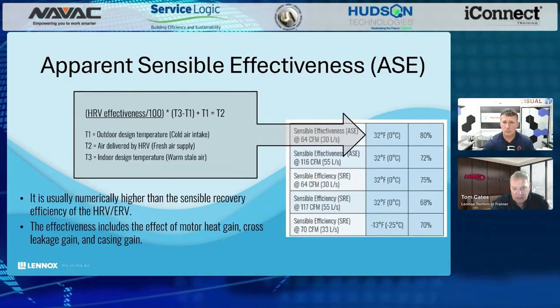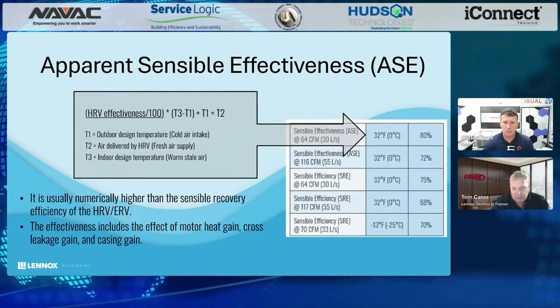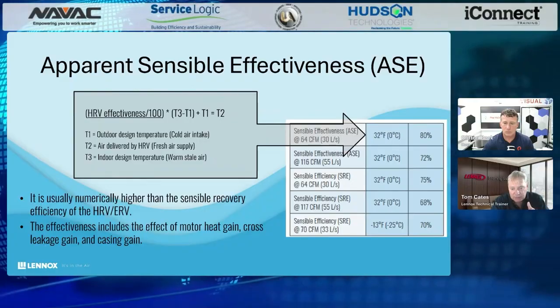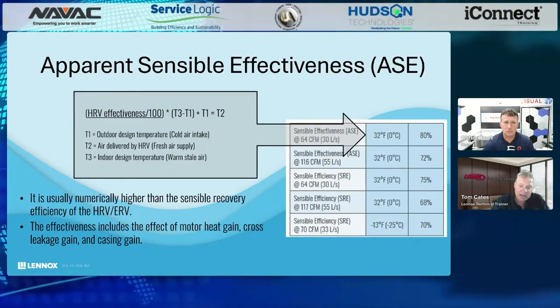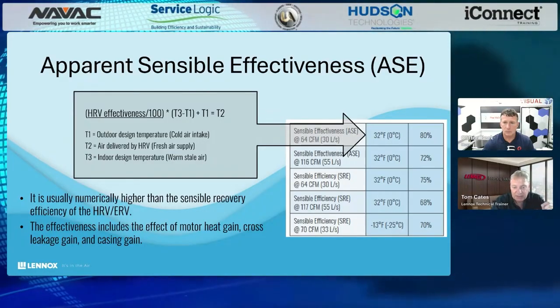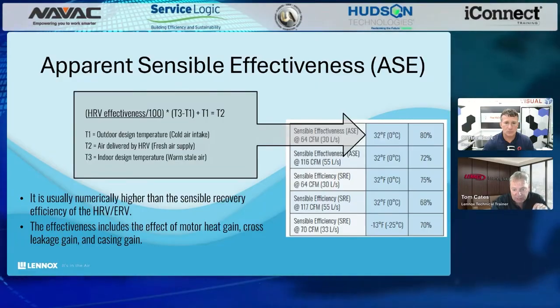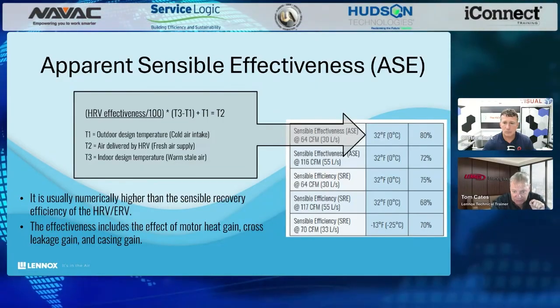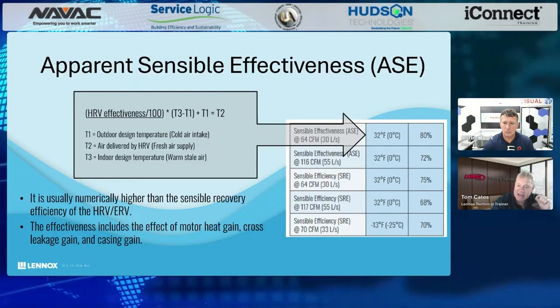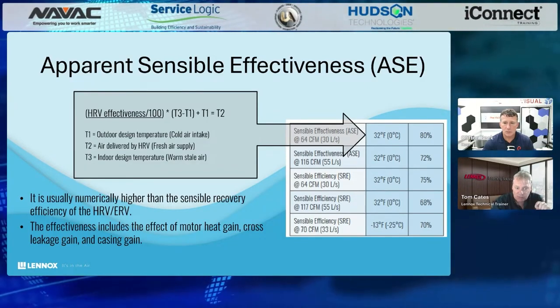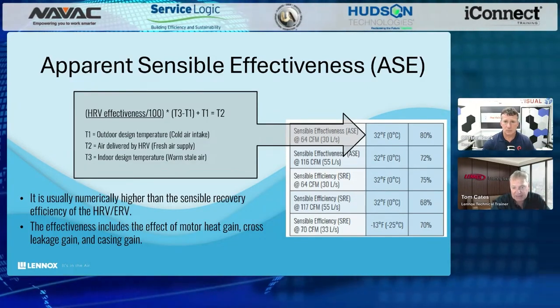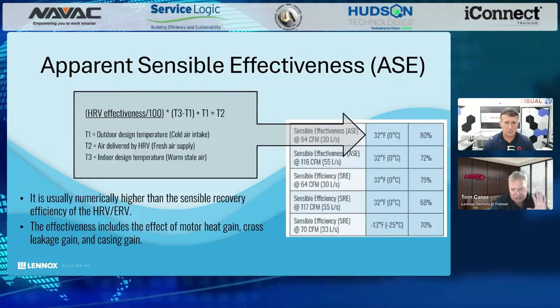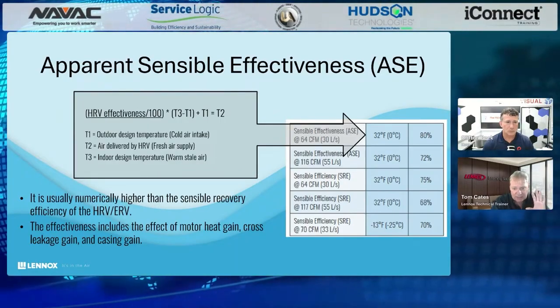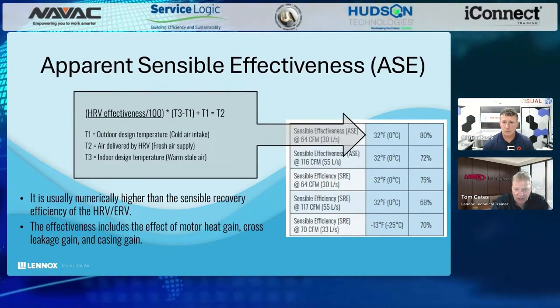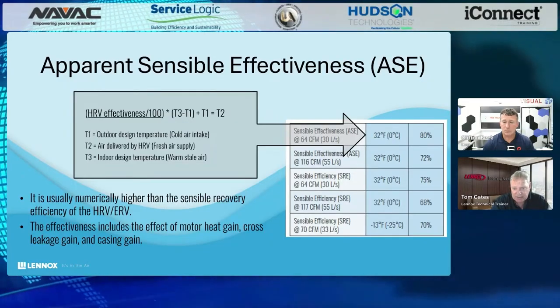If I look at an HRV, we've got ones where the cores are made of aluminum, and others made of some type of plastic. The aluminum core typically does a better job of transferring heat than a plastic core, so an aluminum core will have a higher ASE than a plastic core. Now that's changing through technology, but as a simple understanding of what that number represents, that's what that one is.